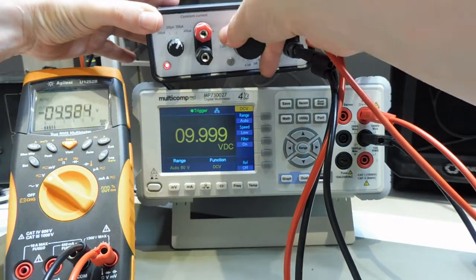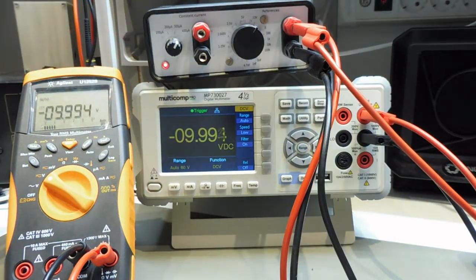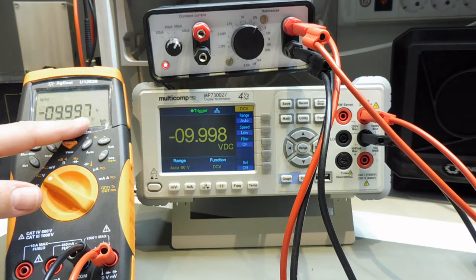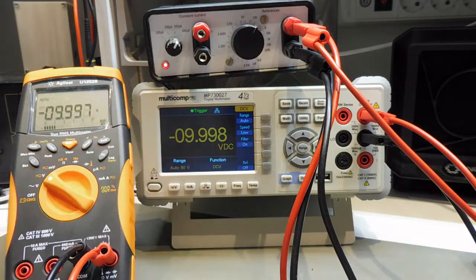And if we switch here, we reverse the polarity. That's the functionality here - I have a polarity switch, so I can easily test whether there are any inaccuracies when reversing the voltage. We can see that it takes a while for the measurements to actually stabilize, but they still look to be within specification. This one here is probably 3 digits low, this one here just 2, so that's very fine.